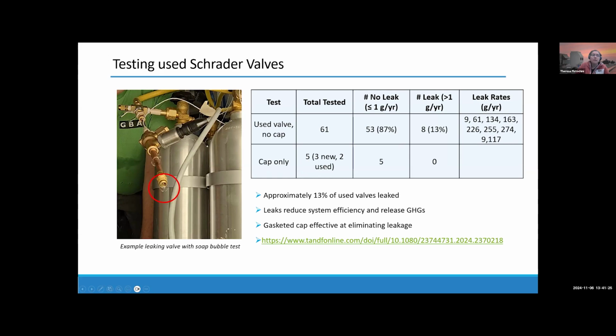Then we took out the valve body and just tested gasketed caps. So in a worst case scenario where your valve is leaking, the gasketed cap completely stops the leak. The big takeaway here is that valves do leak, and we have attempted to quantify that. The implication is that we're releasing refrigerant to the atmosphere, which is a greenhouse gas. We're also reducing system cooling efficiency, or heating efficiency if it's a heat pump. So my message to you today is to make sure you have good gasketed caps on all of your packaged HVAC systems. It's really cheap and you're going to gain something there. And I just have a link here to the publication that describes the leak testing work if you're interested.